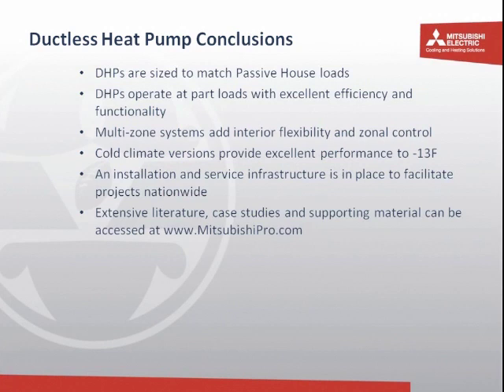There are a couple of options here. The system, as it's generally shipped, has a controller on it that will function in exactly the way that this questioner explains. It has a set point and then will engage either the cooling or the heating side of the system to maintain that set point. And so in a room like a solarium, it's going to have that full range, and it will switch modes during the day to treat that condition.